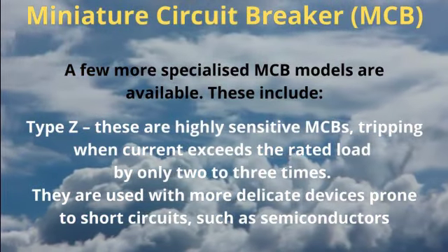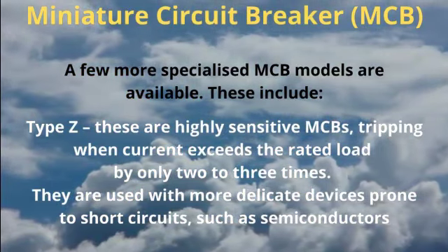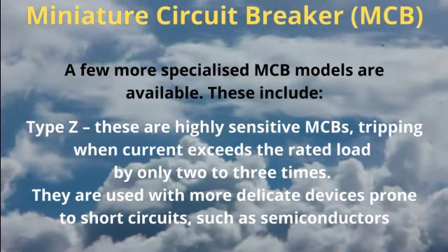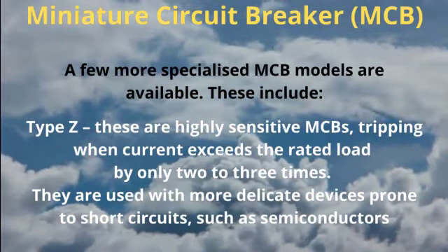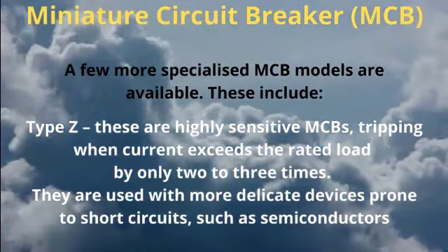Type Z MCBs are highly sensitive, tripping when current exceeds the rated load by only 2 to 3 times. They are used with more delicate devices prone to short circuits, such as semiconductors.